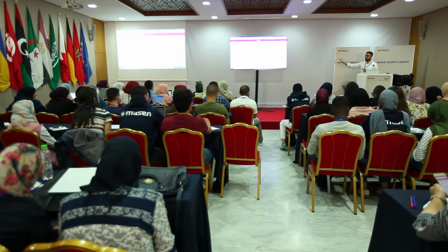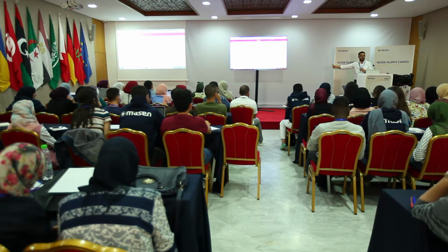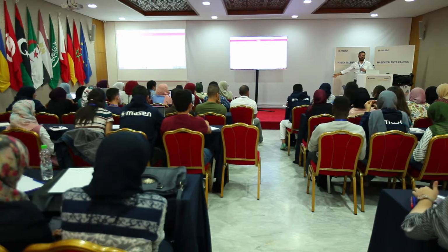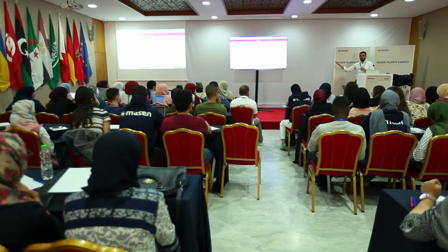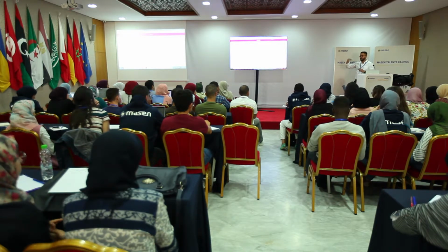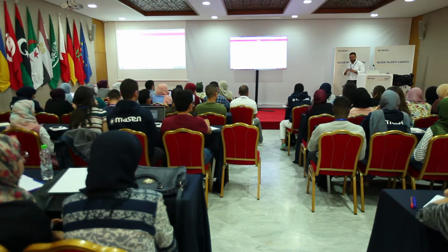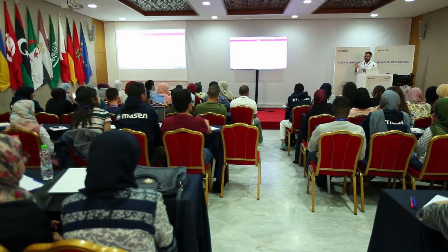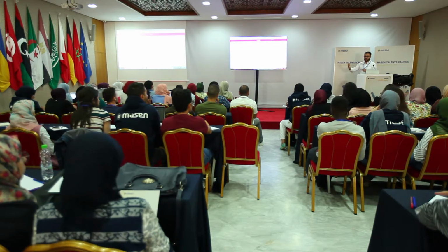If we go to these basic notions, then I just want to keep in mind what are the thermal energy storage solutions we have today commercially available, because there are many in research, but these are commercially available, proven, bankable. In all the parabolic troughs, we have this indirect 2 tanks system, where basically the parabolic troughs have oil. The oil is used to heat up salts that are cold at 285 degrees, and then they get hot. This oil is at 400, so they go up to 395, 390, depending on the efficiency of the heat exchanger. So then you store them hot.